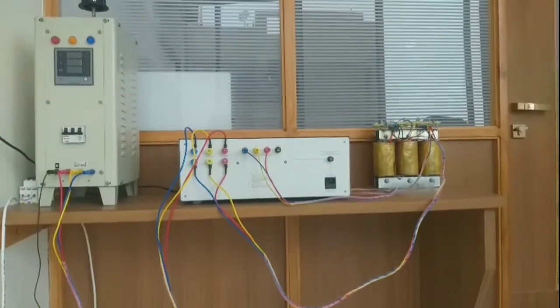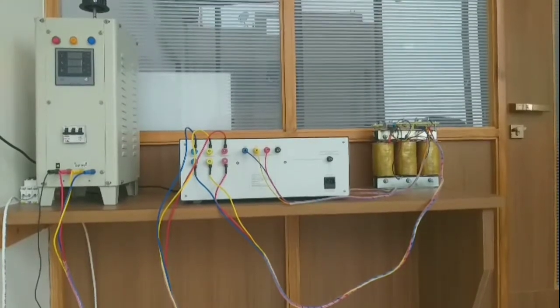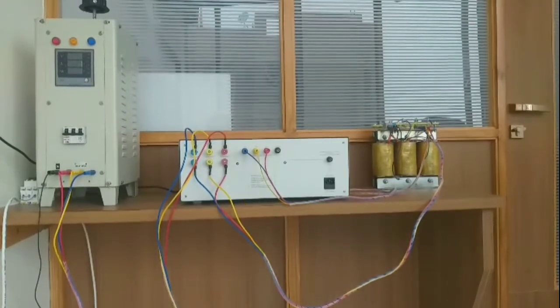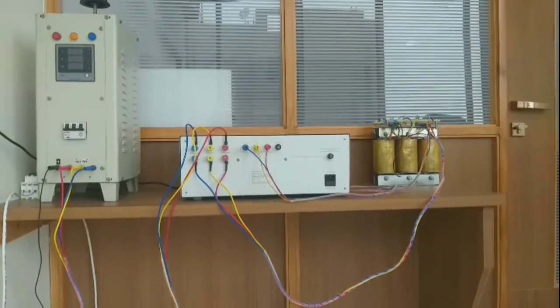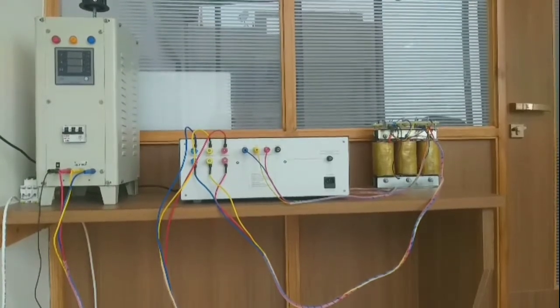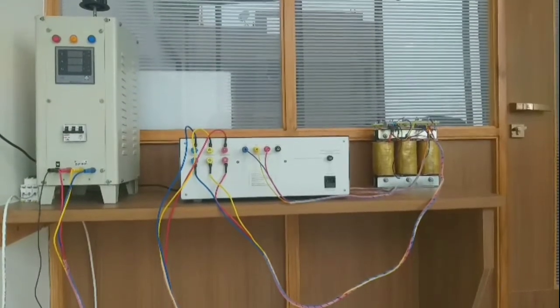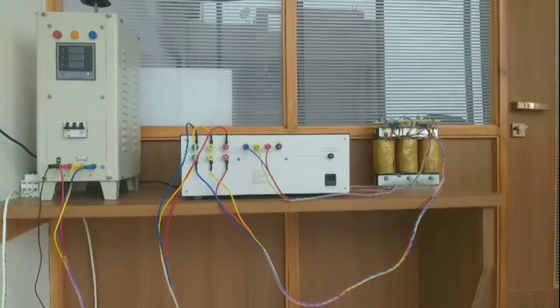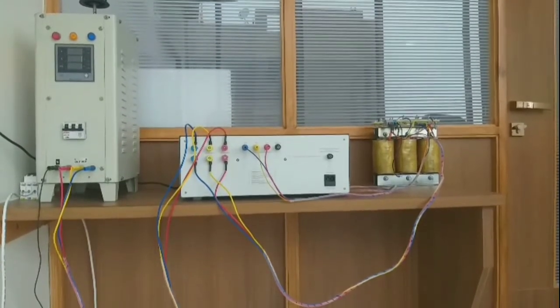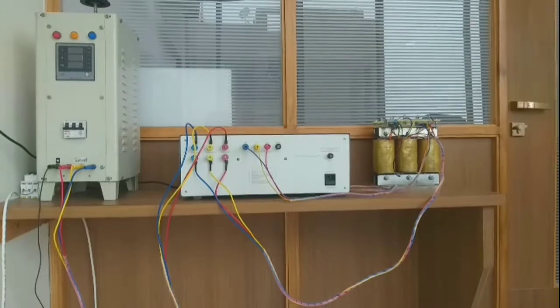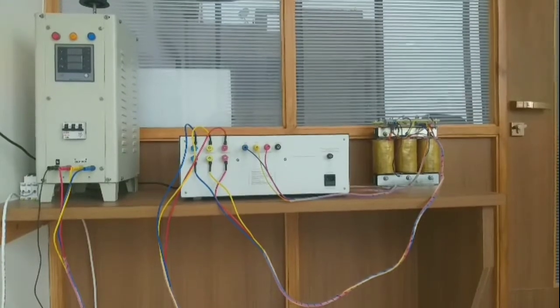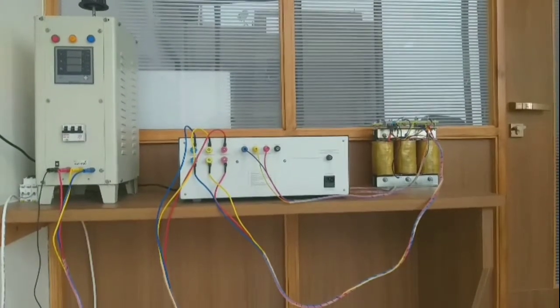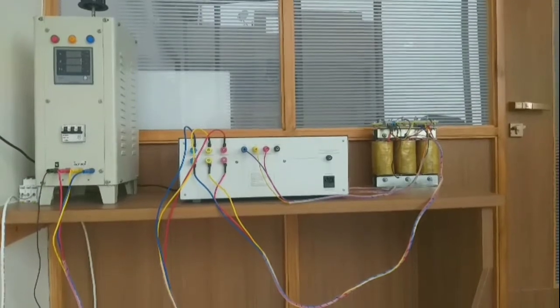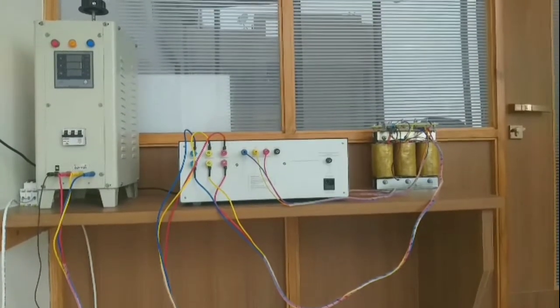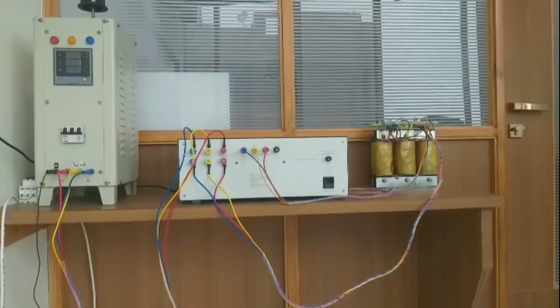We are going to test the no-load test for a three-phase transformer with our power analyzer model DXL 780. First I will introduce the features of the DXL 780. It has 0.1% accuracy, 8 ranges of voltage and current from 5 volt to 700 volt and 0.6 ampere to 80 ampere. It means we can perform the test without using CTPT, from 5 volt to 700 volt and from 0.6 ampere to 80 ampere.